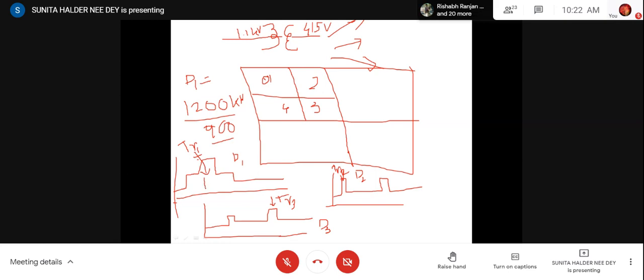But say it has happened that D1 has maximum demand at 10 a.m., and D2 has maximum demand from 10 a.m. to something, say 4 p.m., or whatever span I have taken. Say for this one, I have not drawn properly, it is at 6 p.m. That means the residential load is high. This is also at 6 p.m. So here the residential loads are lesser. So if you interchange some load between these two, then obviously the overall maximum demand of both subblocks will be less, and so the overall transformer size will come out less. You may not have understood. Let me explain it again. Understood?